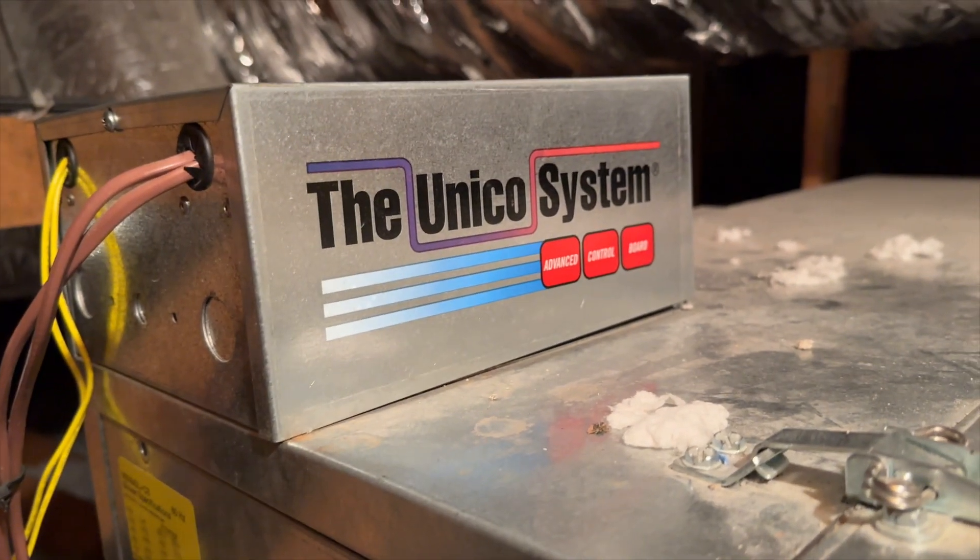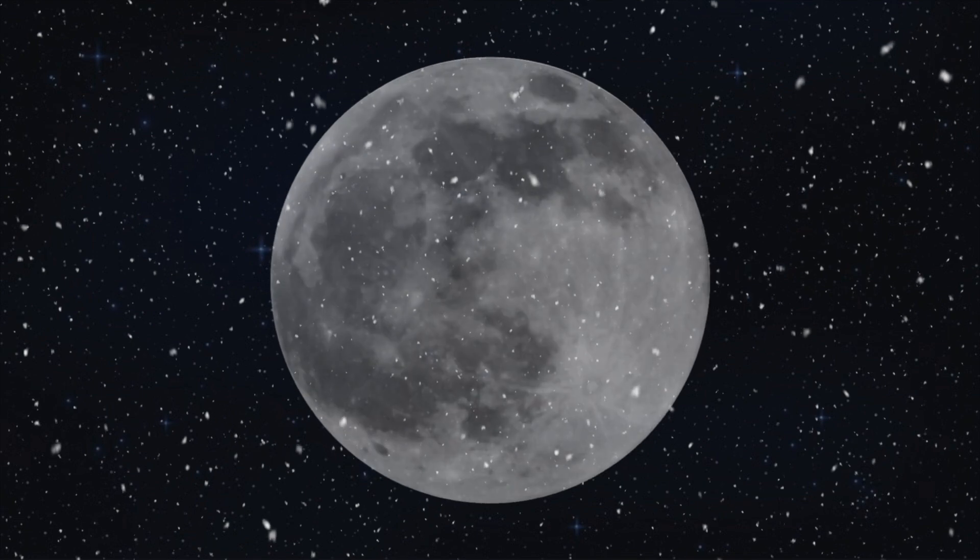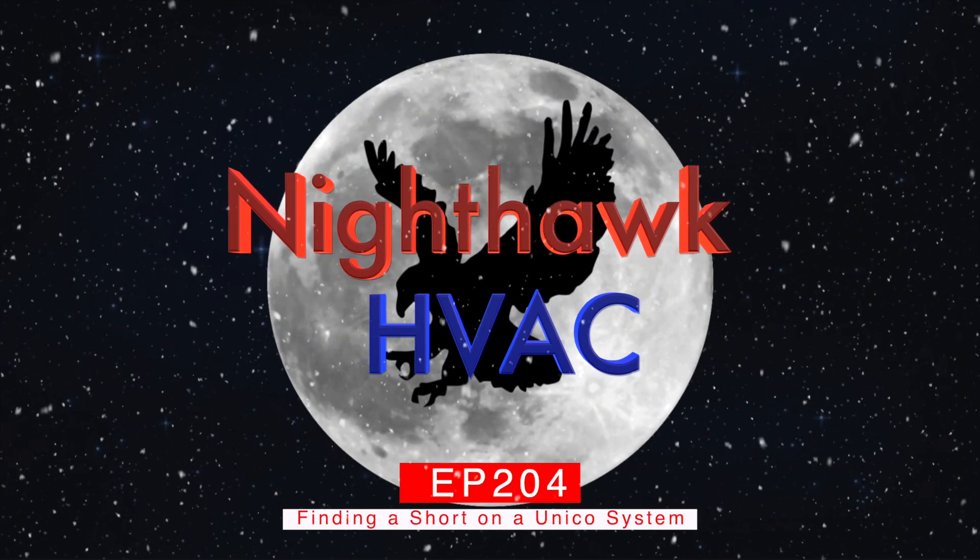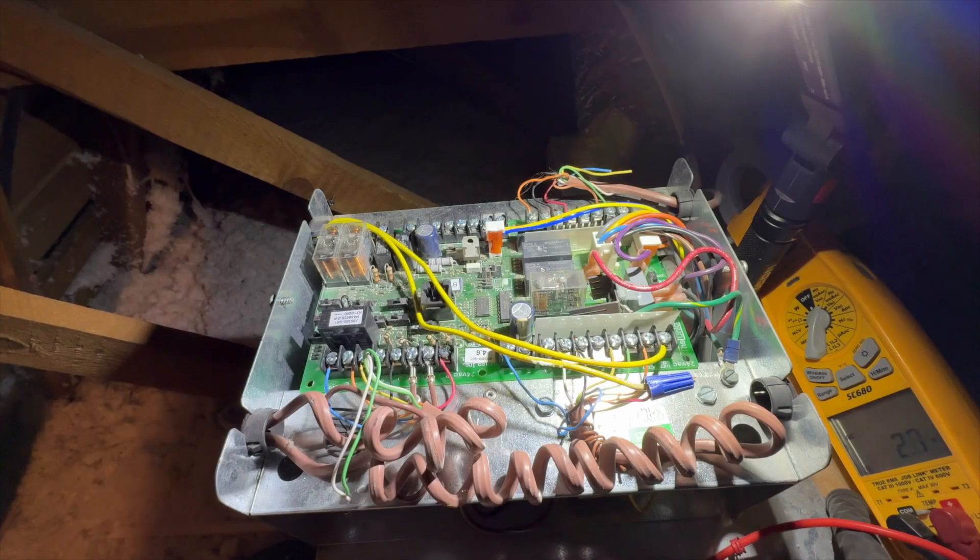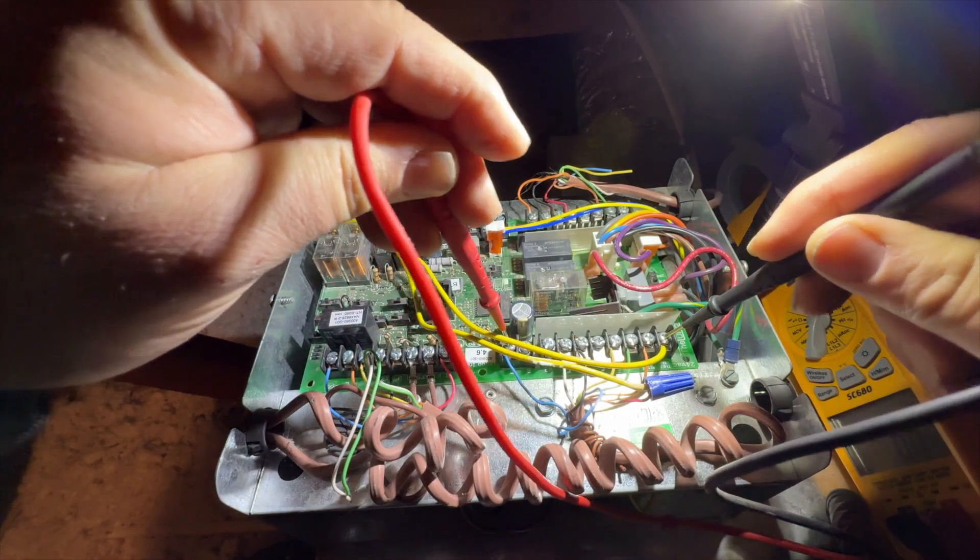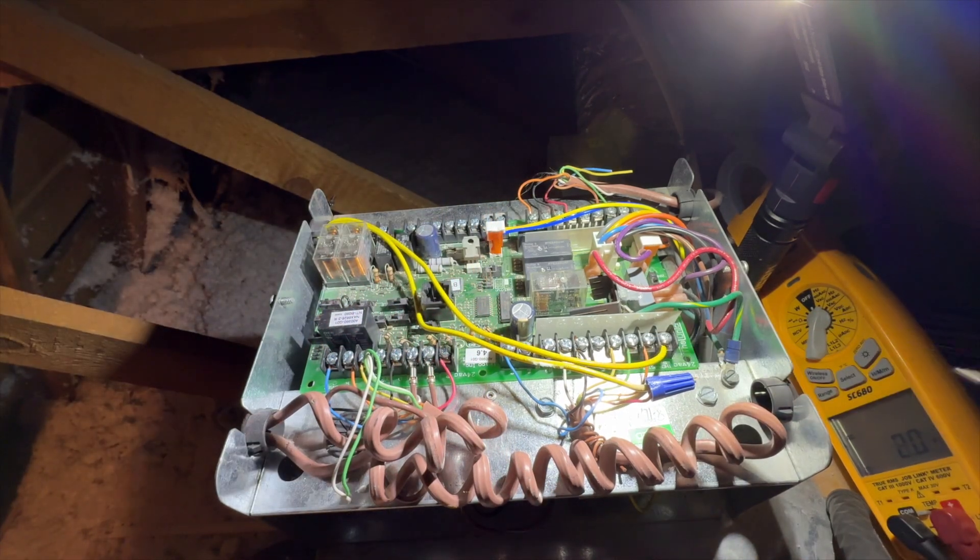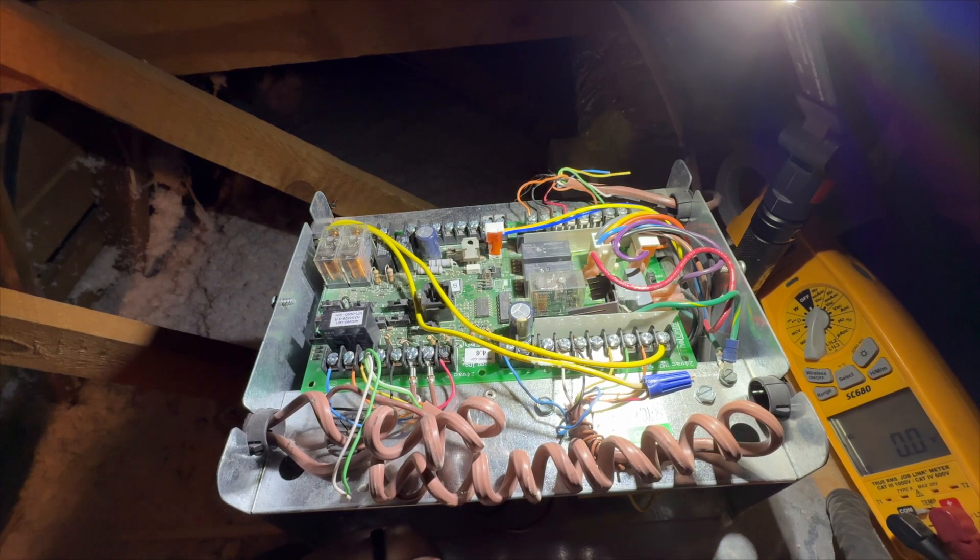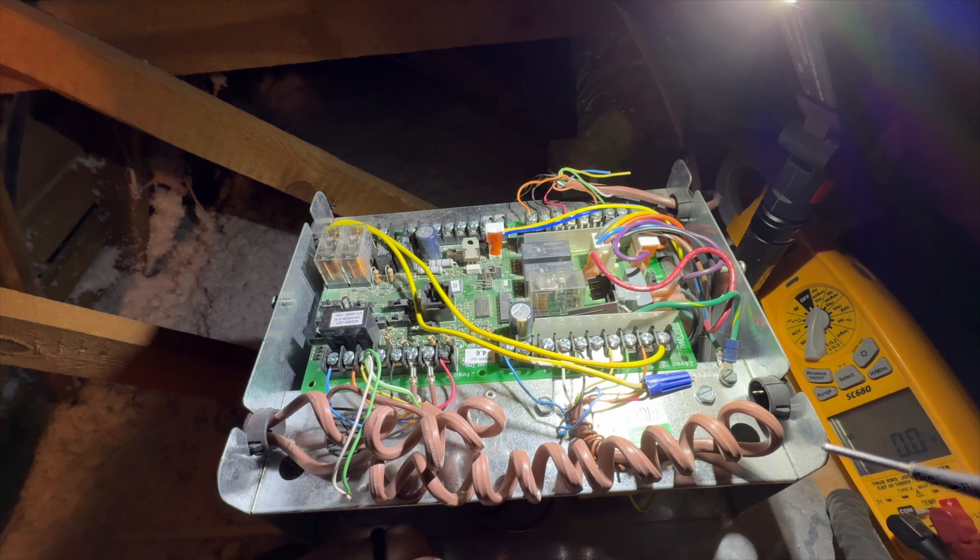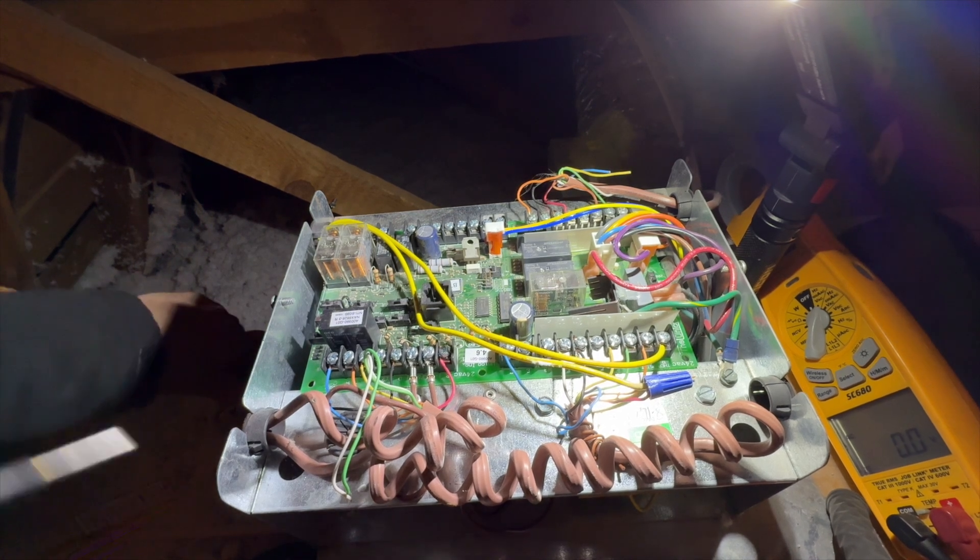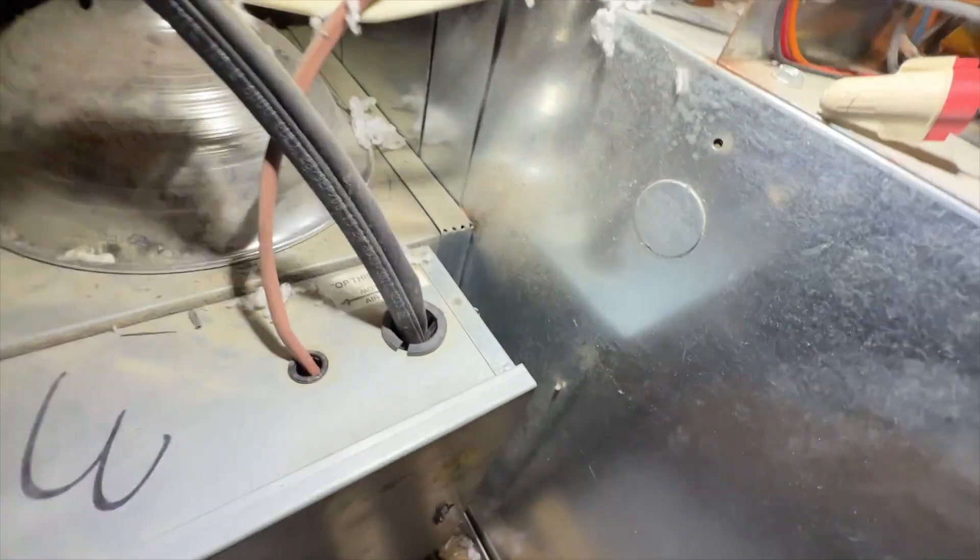All right, we're gonna check for voltage. So we go R and C, and I have nothing. There is a drain switch here but it's not tripped as far as I can see, and I should still be getting 24 volts from the transformer. So either we don't have high voltage or the transformer's dead or there's a fuse somewhere. I don't see any fuses on this, there's no disconnect for this part.